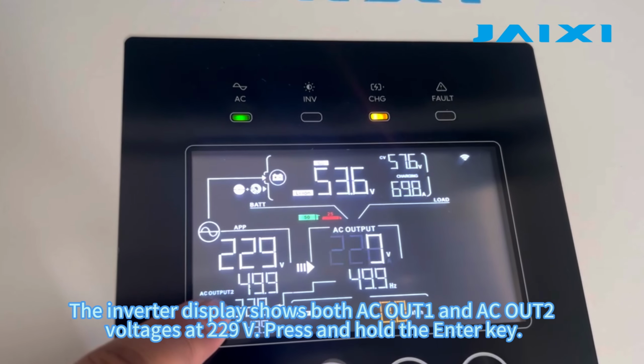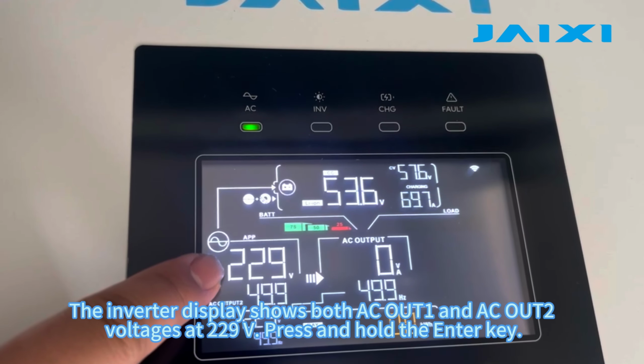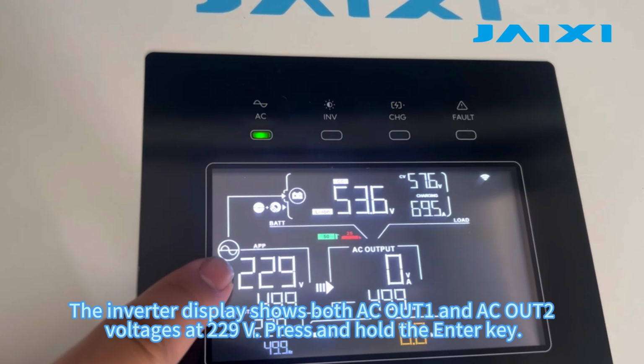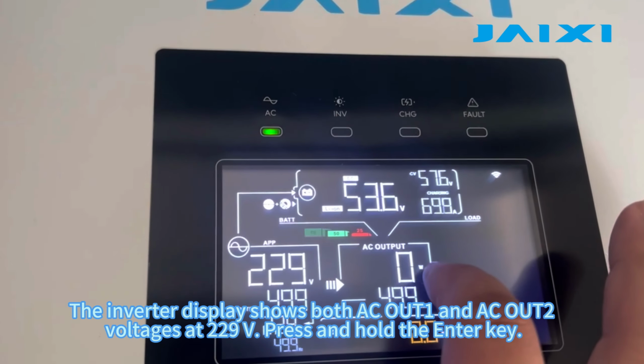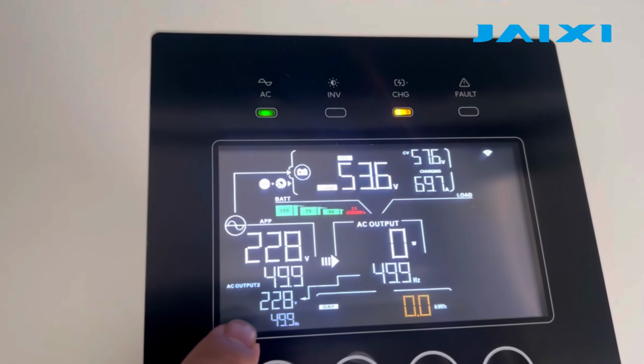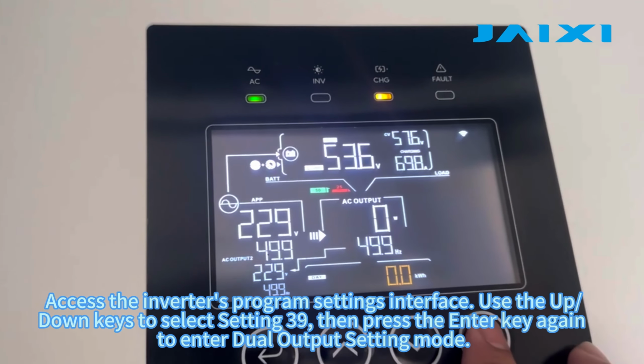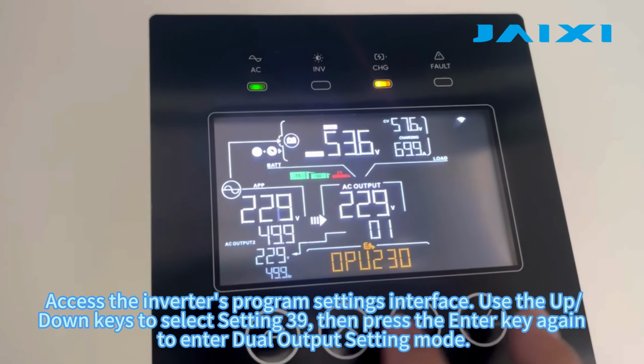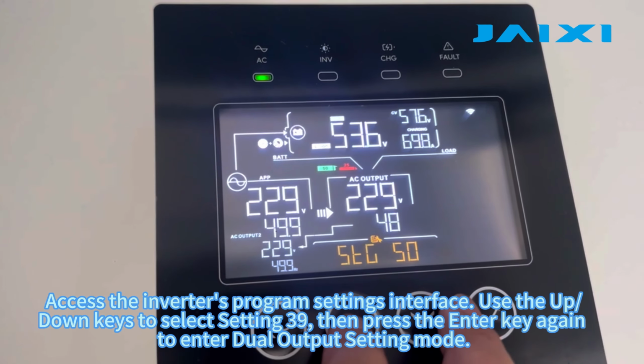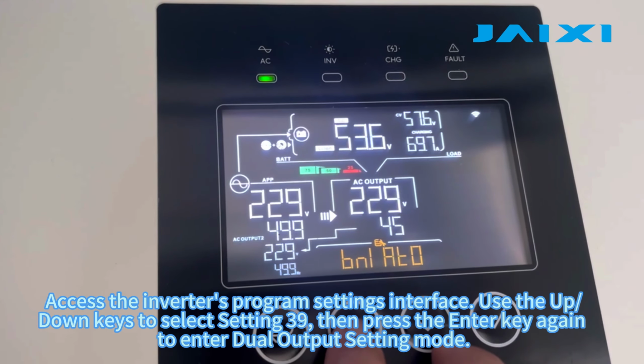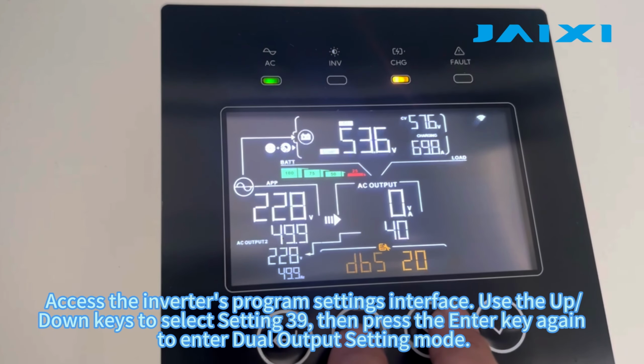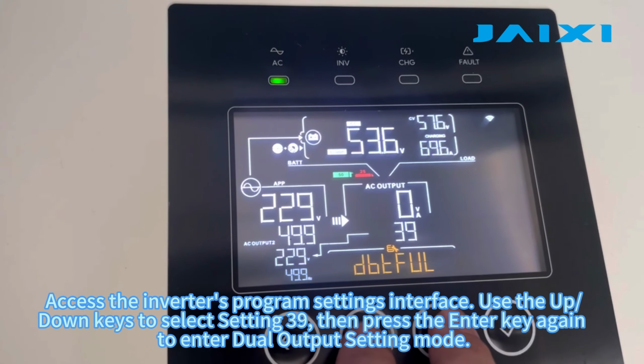The inverter display shows both ACOUT1 and ACOUT2 voltages at 229 V. Press and hold the Enter key. Access the inverter's program settings interface. Use the up-down keys to select setting 39, then press the Enter key again to enter dual output setting mode.